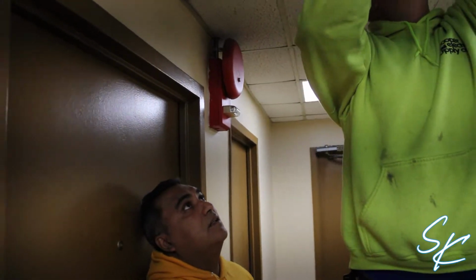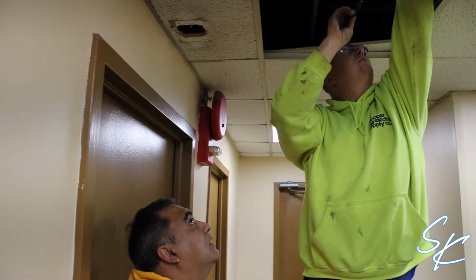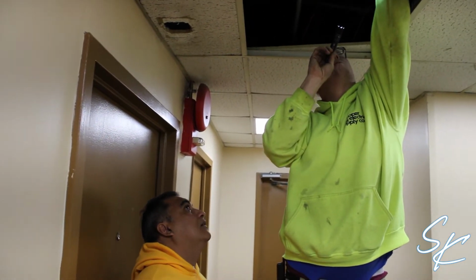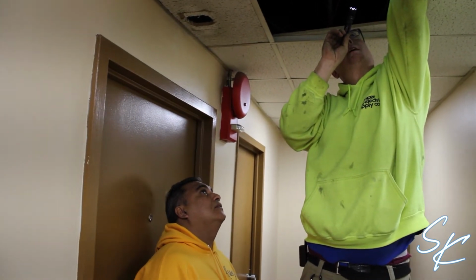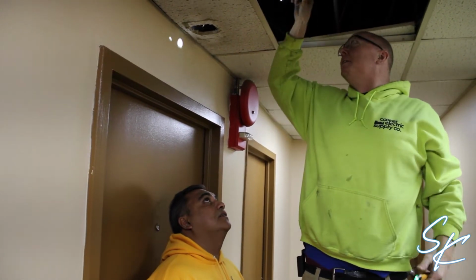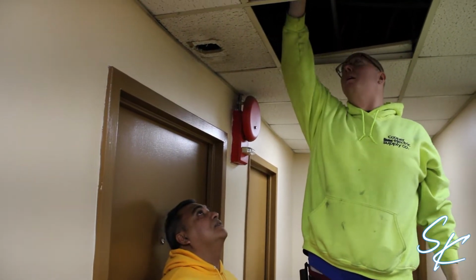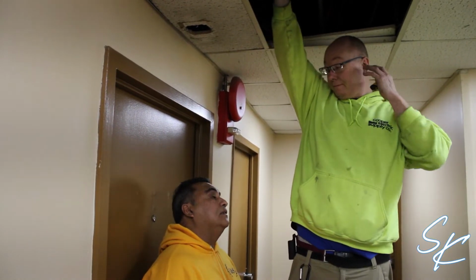That one's right coming out of another junction box over there. You can see the insulation coming out of this wire nut. The wire nut's too small for the wires, or they stripped it back. So that's live and that's hanging out pretty close to metal, so that's close to arcing. This was miswired. It's wired out of a junction box without a cover on it, just sitting up here.